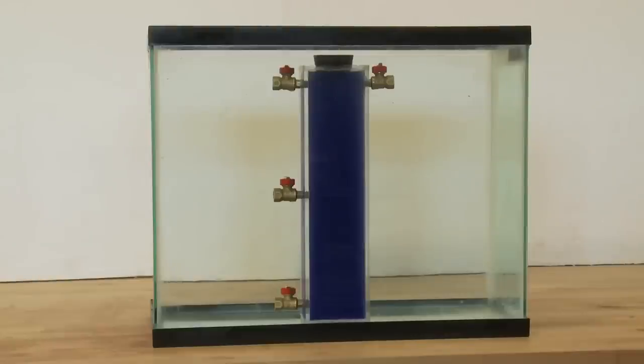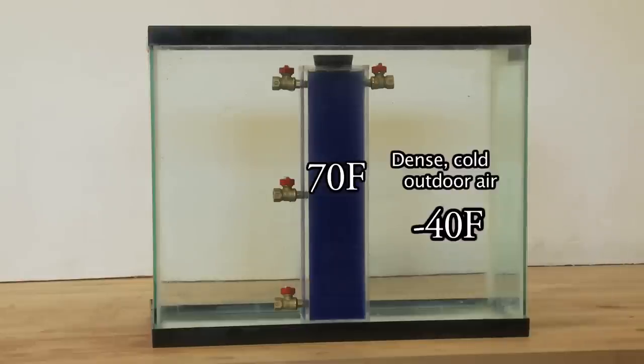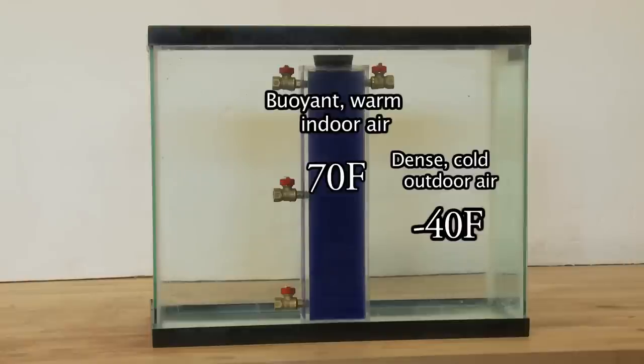When it gets very cold outside, let's say it's 40 below outside and inside it's 70 above, that's a 110 degree difference in temperature. What that difference in temperature does is it creates very cold, dense, heavy air outside in relation to lighter, more buoyant air inside. That's your pressure difference.